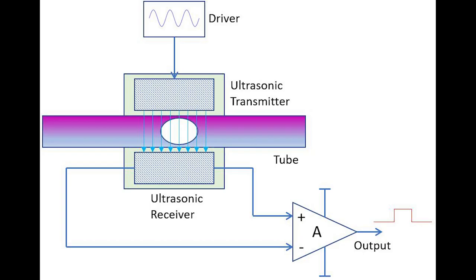Inside the flow sensor there's a crystal which sends out a piezoelectric wave. The wave will continue across the gap to a detector as long as there's a medium, like a liquid, that's present to continue conducting that wave and transmit the signal across the gap.